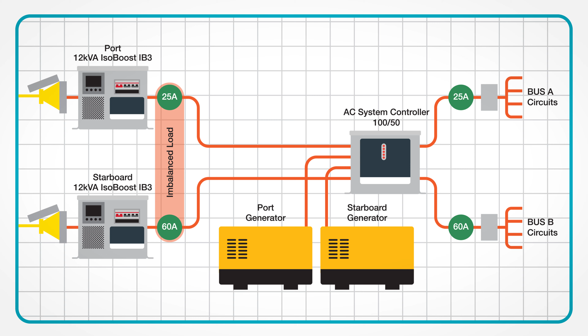amp IsoBoosts, an AC changeover and two groups of circuits. One of those groups of circuits is well within the capabilities of an IsoBoost, 25 amps. So we're loading it at 50%. But the other group, let's say air conditioning, is running flat sticks and it's actually pulling more than the continuous output of the IsoBoost and shore cord at 60 amps. In this case, we're eventually going to see a shore power breaker trip or an over temperature on the IsoBoost and the protection trip being activated on that.